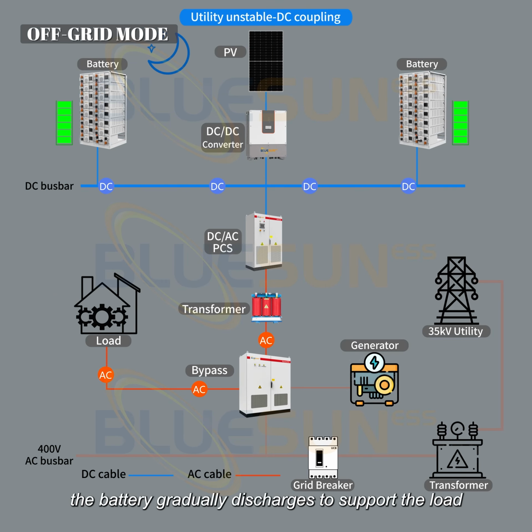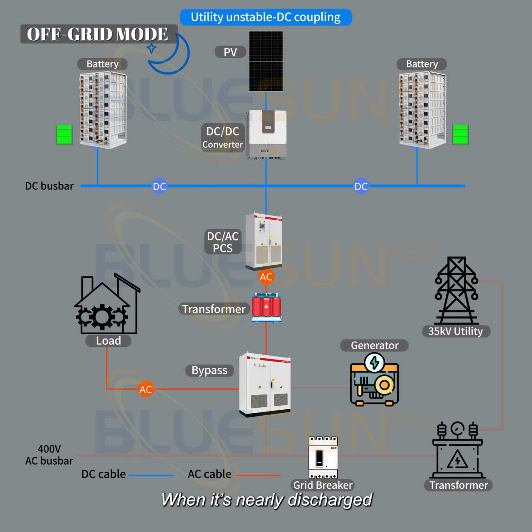At night, the battery gradually discharges to support the load. When it's nearly discharged, the PCS stops discharging and uses the diesel generator to directly power the load via the bypass.